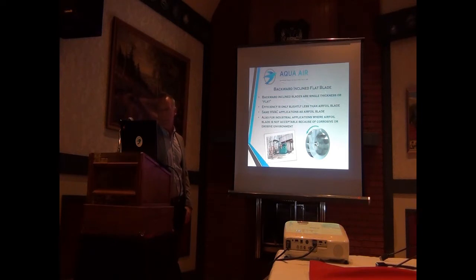These fans are backward inclined, and with an airfoil blade you get efficiencies in the 80 to 85 percent range, which I forgot to mention on the forward curve. There you're probably looking at a max of 60% efficiency. The backward inclined and the airfoil blades have the same HVAC applications. They're most often found in moving primary air within an air handling unit. They're also used for industrial applications where an airfoil blade is not acceptable because of corrosive or erosive environments.